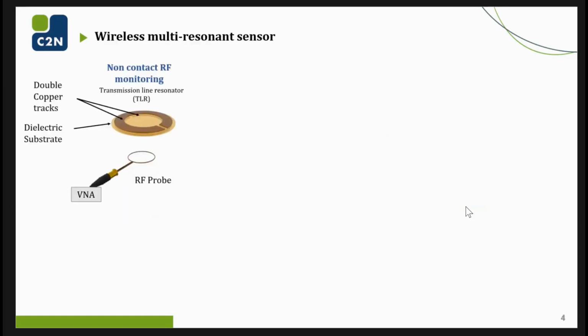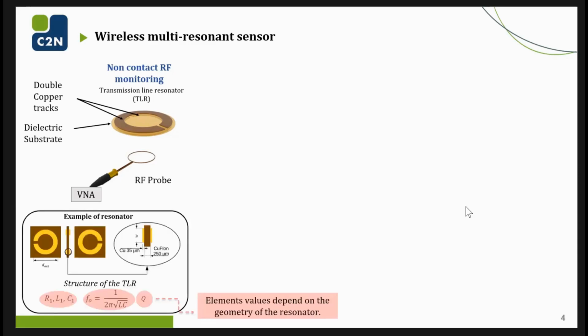So the sensor in question is a resonator based on circular transmission lines. It is constituted of two copper tracks that are deposited on a dielectric substrate. It is remotely activated at a certain frequency through an inductive coupling with the radio frequency probe, which is made from a wire loop coil and connected to a vector network analyzer. The resonance frequency of this resonator, its electrical elements and quality factor are determined by its geometry. So it depends on the diameter, the thickness, and the width of the copper tracks and the thickness of the substrate. With this kind of configuration, we can get one piece of information at one frequency.